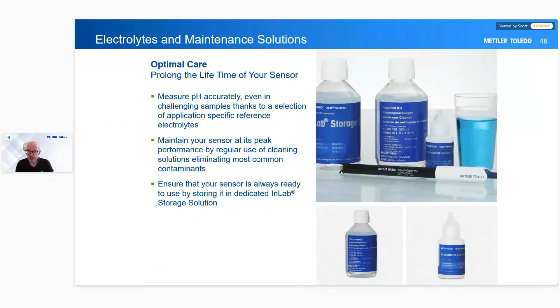The next one is looking after this gel membrane. So if the gel membrane dries out, what happens is we get unstable readings or we can't get stable readings, and that's caused by dry membranes. And that could be caused by either non-aqueous solutions, or we've used ion deficient media, we've used the wrong storage, or an old sensor as well. So when we talk about old sensors, what we mean is this gel layer has a lifetime. This gel layer eventually gets loose and flaccid. Over time, it just dissolves away, and eventually it will get old and just wear out and not function the way it's meant to. And that's just the normal life of an electrode.